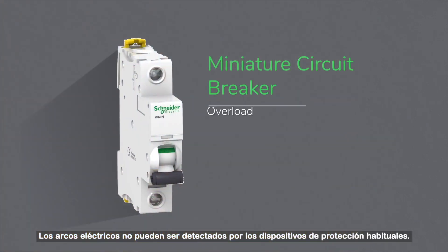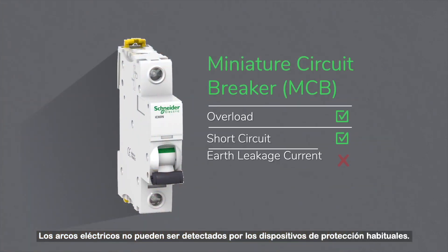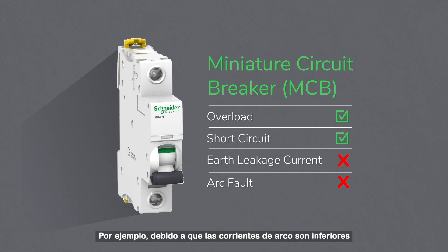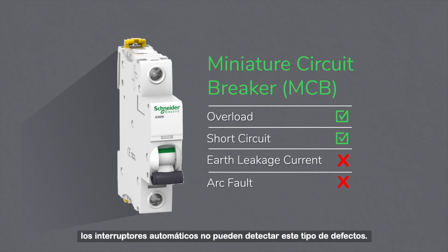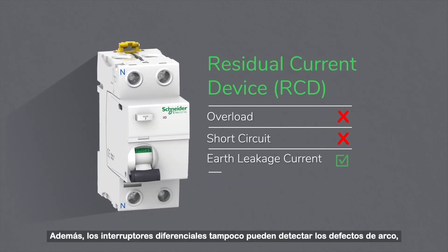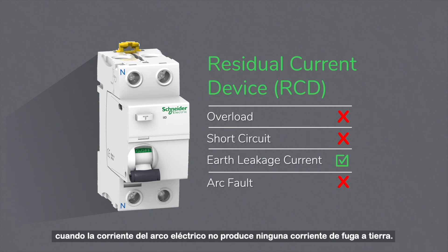Electric arcs cannot be detected by common protective devices. For example, because arc currents are lower than rated or short circuit currents, MCBs cannot detect such type of faults. Furthermore, RCDs are unable to detect arc faults as well, when the arc current isn't producing any earth leakage current.